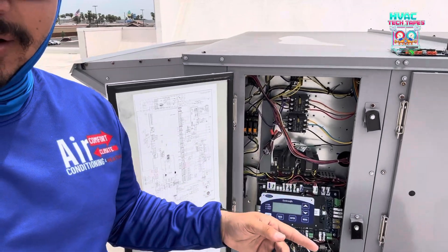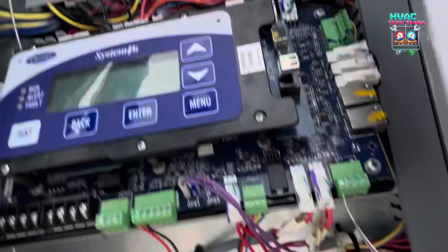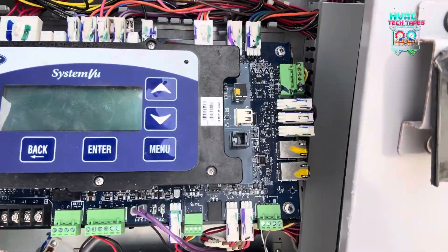All right, next call. We're here in Mission. We got another RTU unit. This one's throwing an error code: A099. That means it has a lost connection with the SIOB board — that's going to be this little board down here. We've got the SystemVu on this one too.